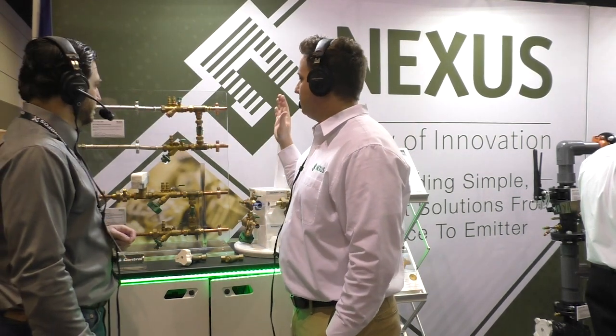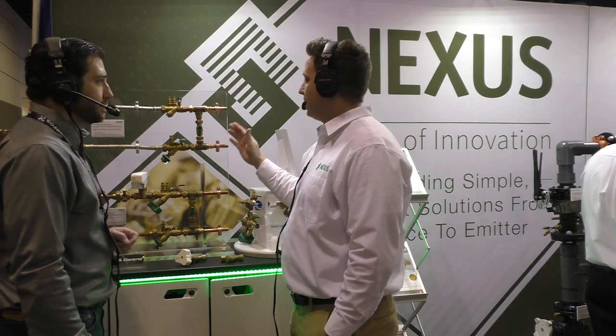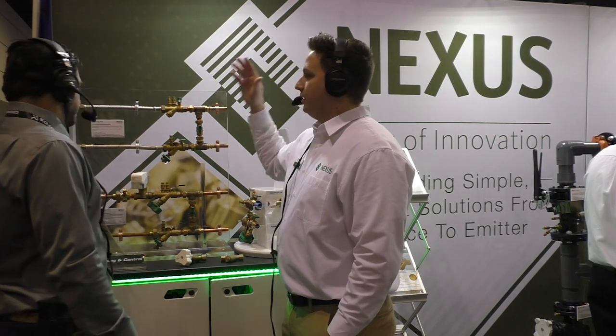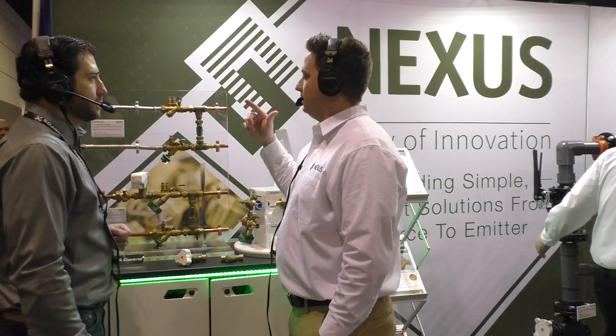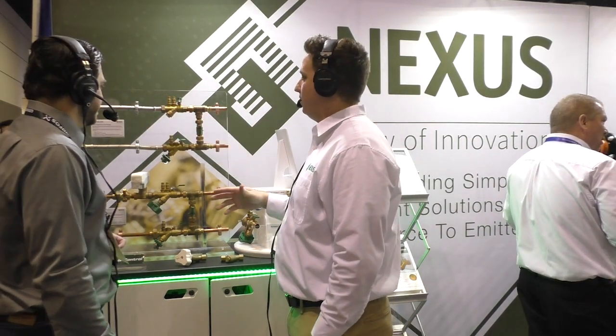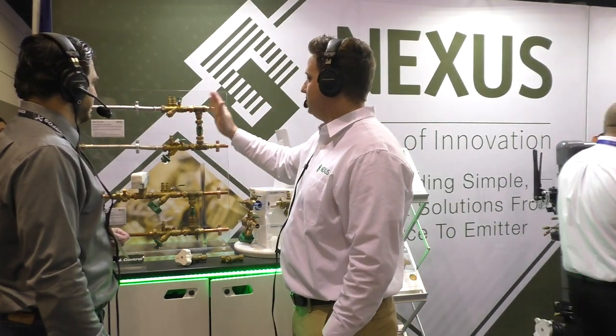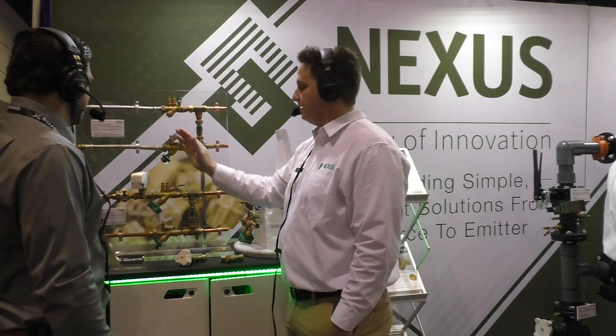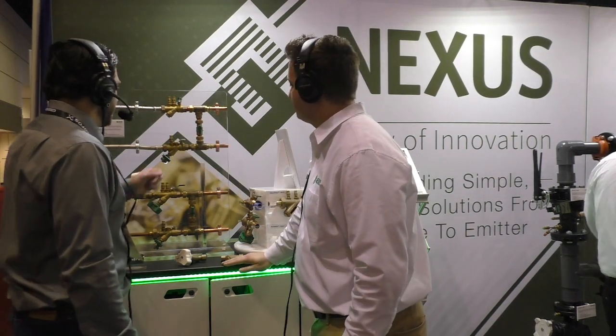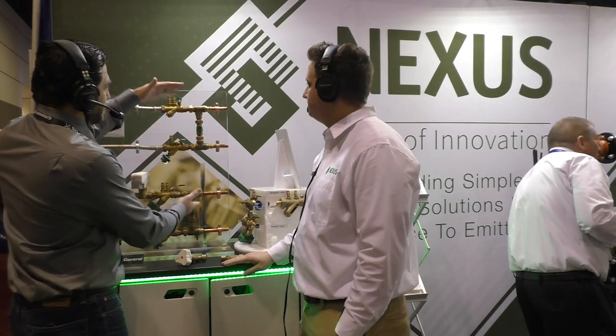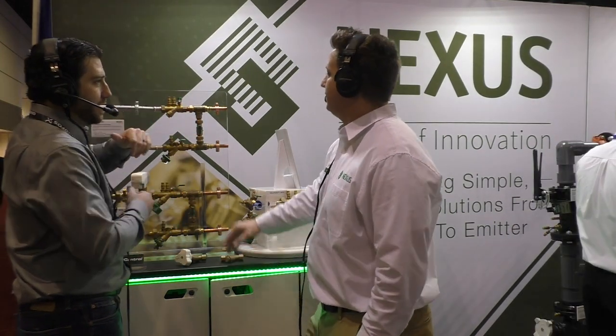Because typically with any type of flushing, forward or backward, you don't want to go through cartridges, orifices, coils. This gives you the ability to completely isolate from all the main equipment. We're showing it here directly piped from the supply return, but they could also extend that with a nipple if needed.